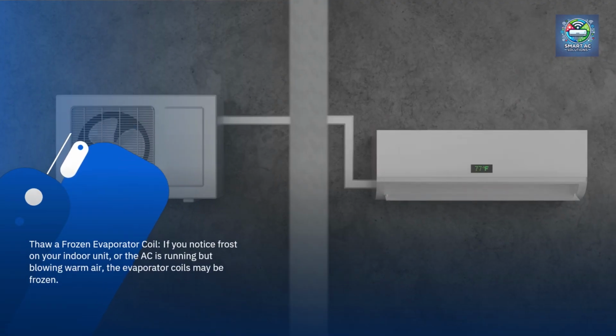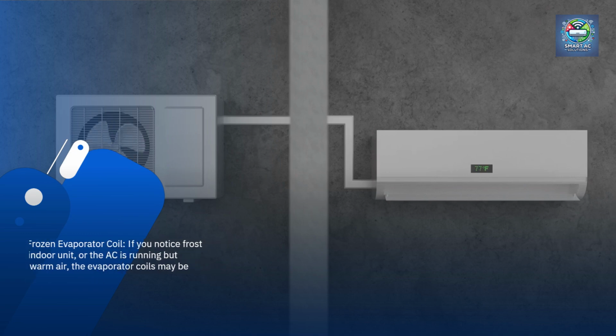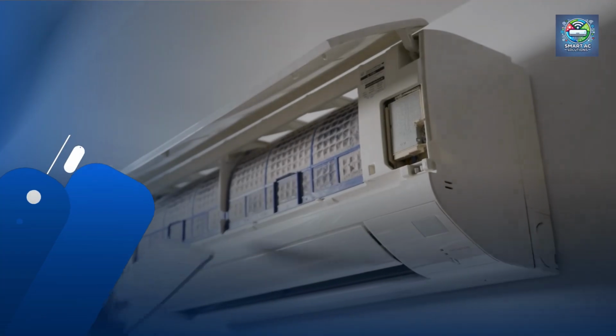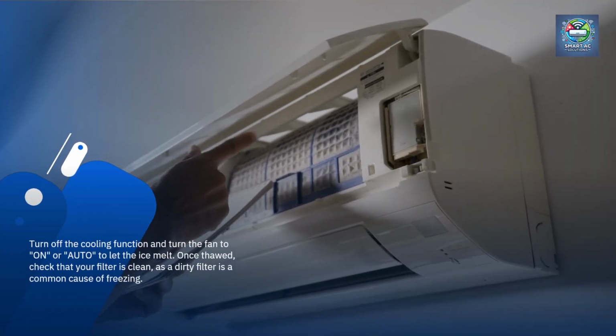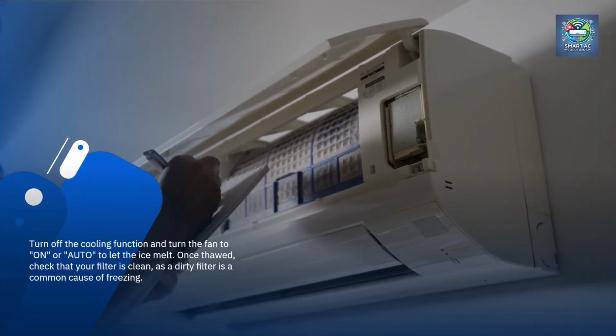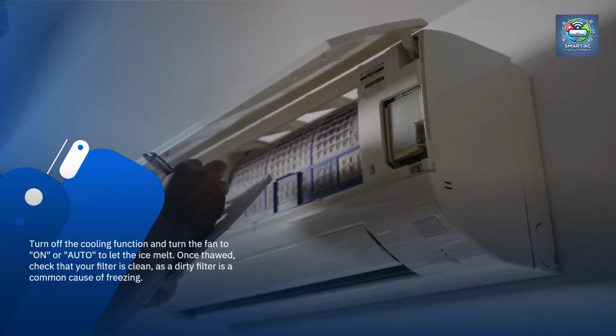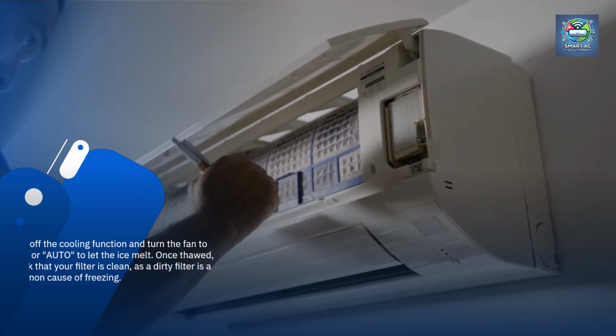Thaw frozen evaporator coil. If you notice frost on your indoor unit, or the AC is running but blowing warm air, the evaporator coils may be frozen. Turn off the cooling function and turn the fan to on or auto to let the ice melt. Once thawed, check that your filter is clean, as a dirty filter is a common cause of freezing.